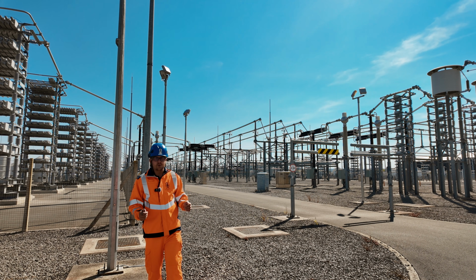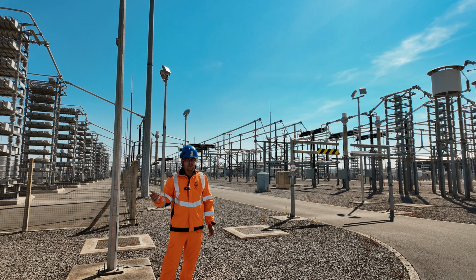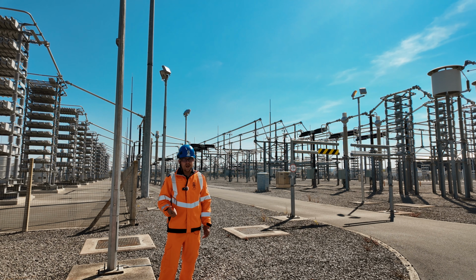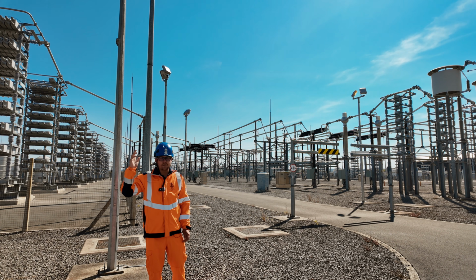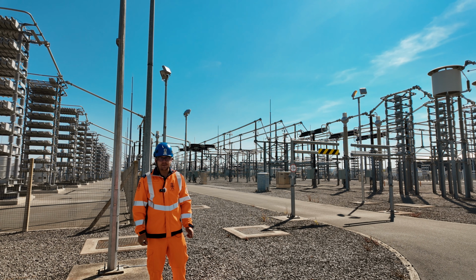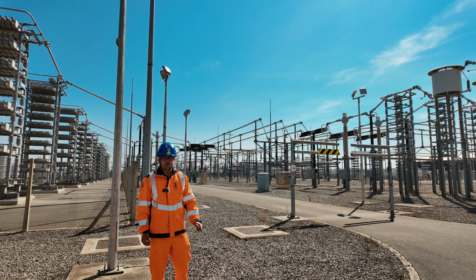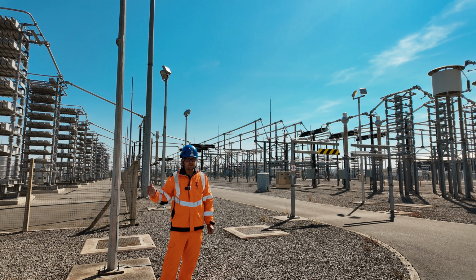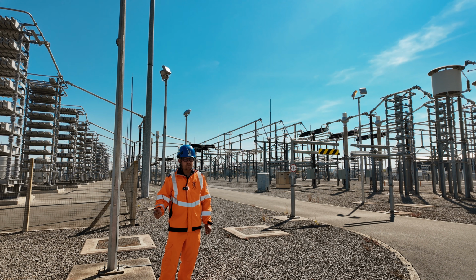If you're wondering why all this equipment is low down, at 400 kV, one thing is that the capacitor bank would be a stupidly high tower if it was at our normal clearances up in the air. And it would be a nightmare to maintain, since there's hundreds of individual capacitors across this site, and a few fail every year and need replaced. And because it's low down, we have a fence around it so you can't get near, with the gate being interlocked so you can't get in while it's live.